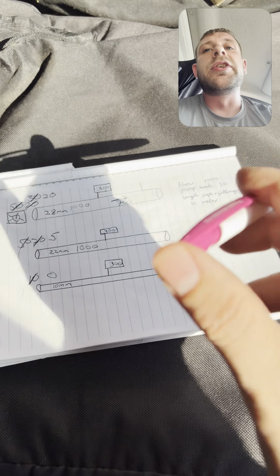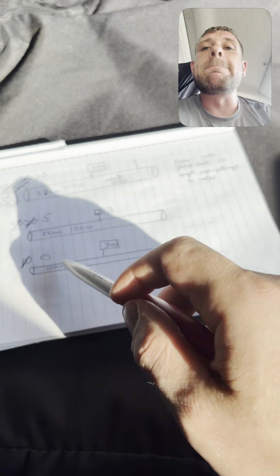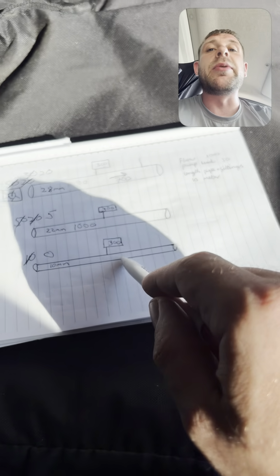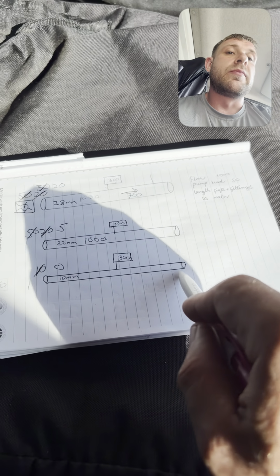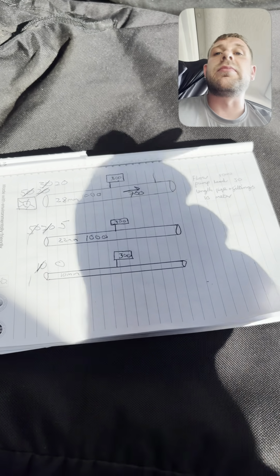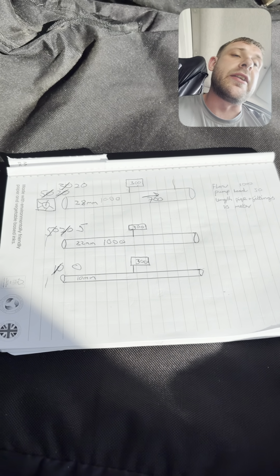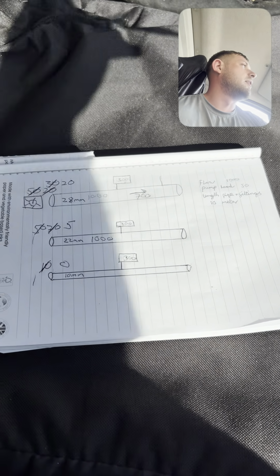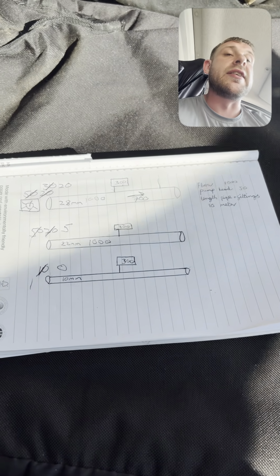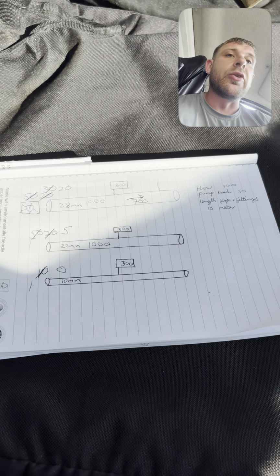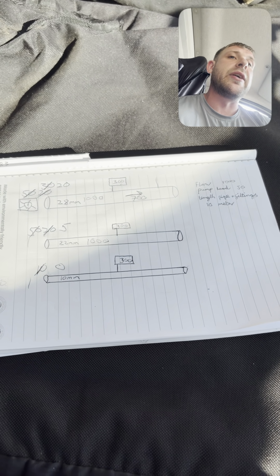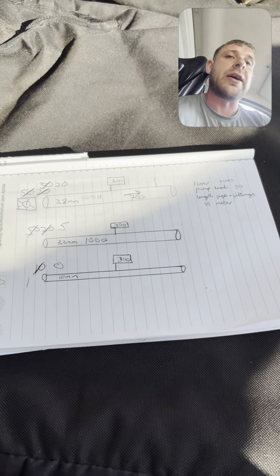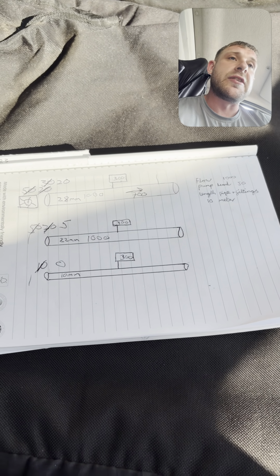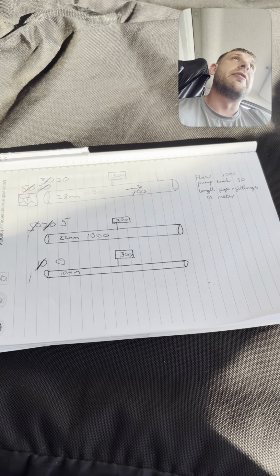You can, where we've got pipe that's carrying a larger amount of flow rate, and we've got a lot of pressure loss in some part of the system, or leading to one of your radiators, we can upgrade the sizes of that pipework, so then we have less resistance in that pipework and less pressure loss. So that's one way around things.